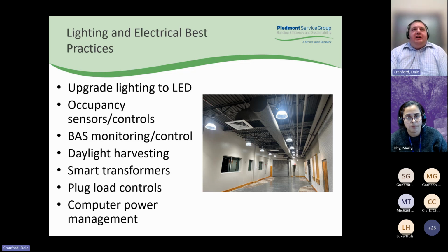And then you can use that trend data with the fault detection and diagnostics as well to monitor and control your lighting and make sure that in a lot of cases someone's coming in after hours. You're able to figure out why that's happening and why it's causing your lights to maybe run more than they should be. Another technology we implement is daylight harvesting. So there's sensors that can be installed that help dim lights during the day or even turn them off when there's enough daylight present to illuminate the room and reduce energy consumption there.